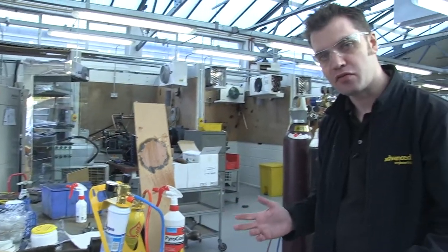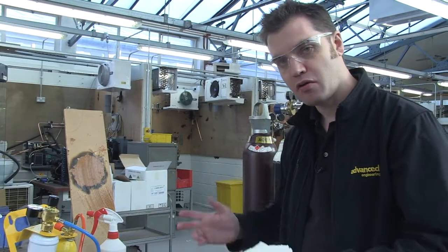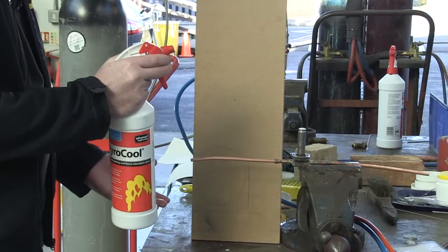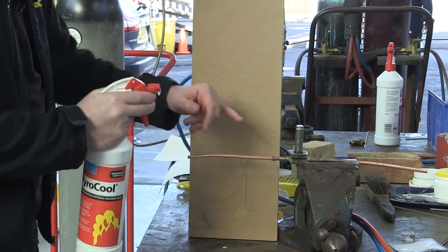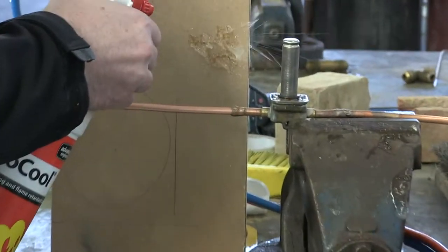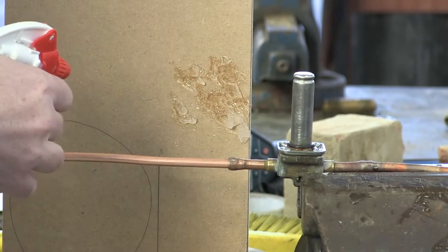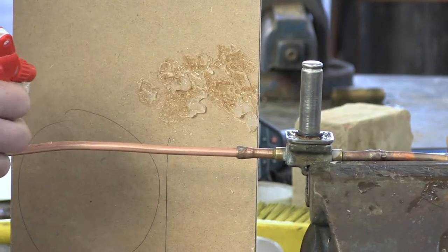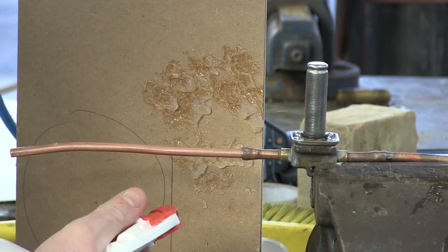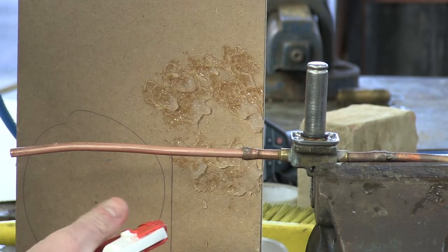We will now move on to demonstrate Pyrocool being used to protect the surface while doing a braze. I'm now going to apply the Pyrocool behind where we're looking to create the braze joint. Again, you want to provide a liberal coating over the entire surface that you need to protect, ensuring a thick, even covering.